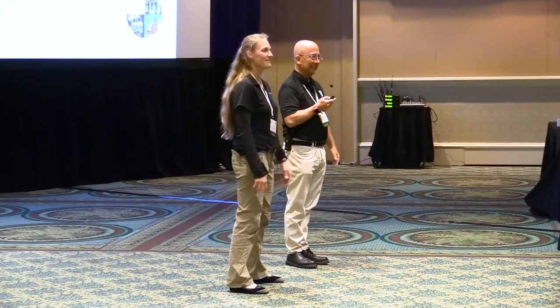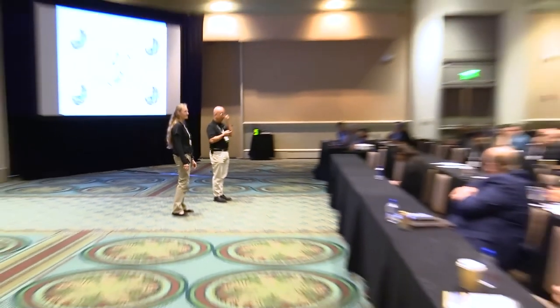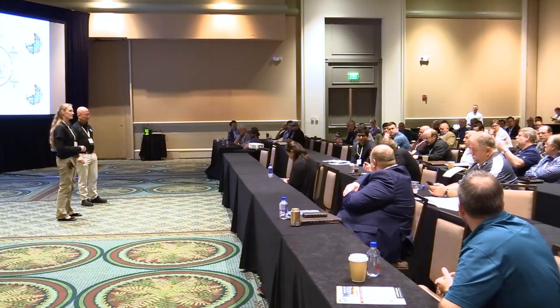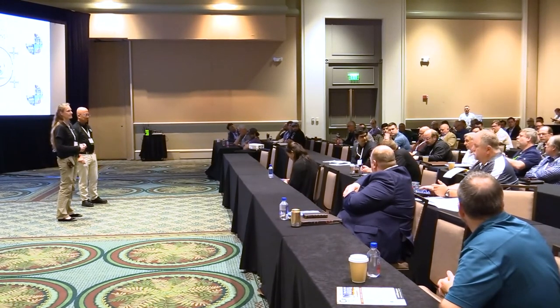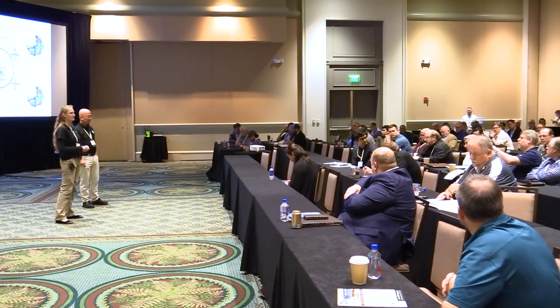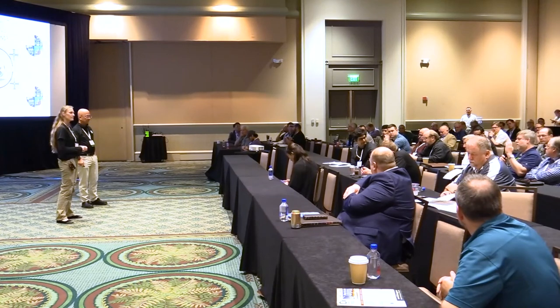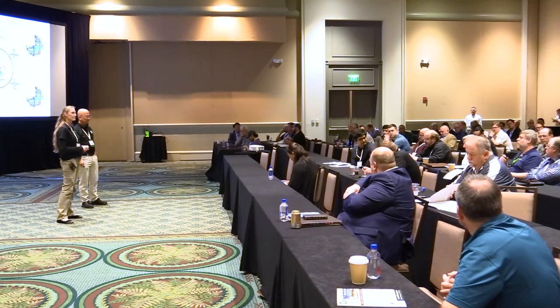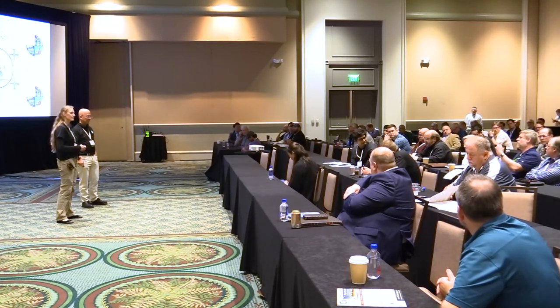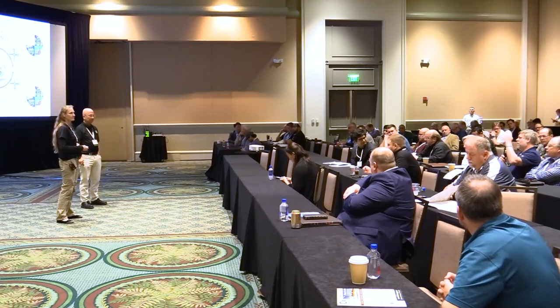Sure. Yeah, thanks for the presentation. Good presentation. A couple questions for you. Maybe one comment and one question. One thing I didn't see on there, which I'm sure you've run across, is what we call a service mode. It's where you actually turn the equipment off to do service. There'll be controls that show how they're going to ramp down chillers and how the valves will behave. But if you need to command it off or literally flip the disconnect switch, what's going to happen? That's usually an eye opener for many of the engineers and teams we're working with. So make sure you're able to shut it down for service, emergency maintenance, whatever you want to call it.